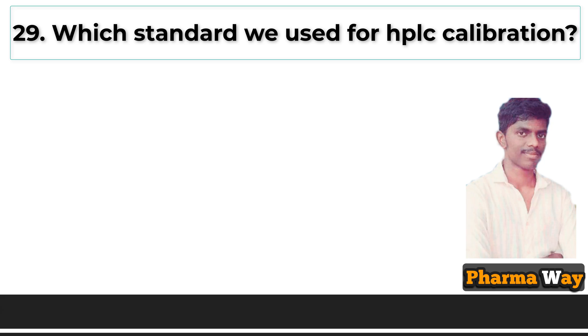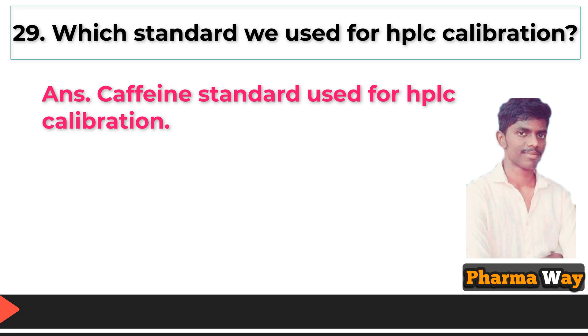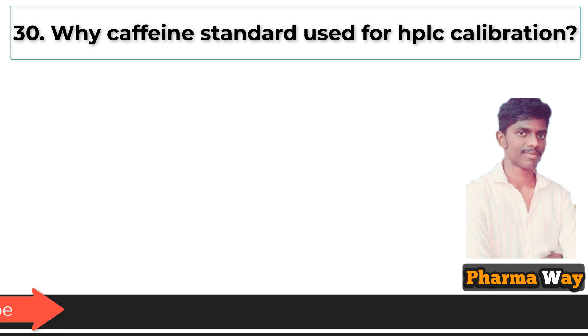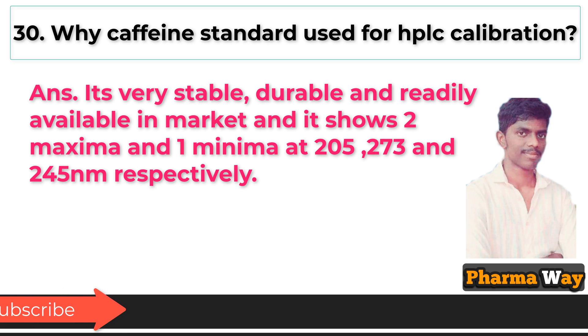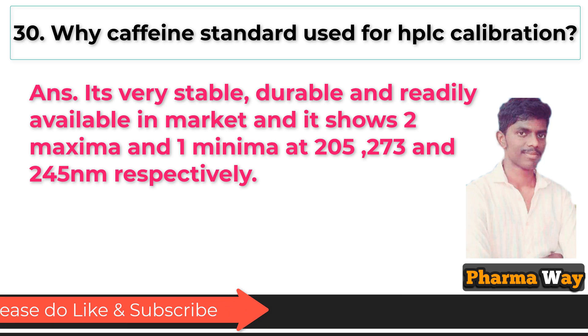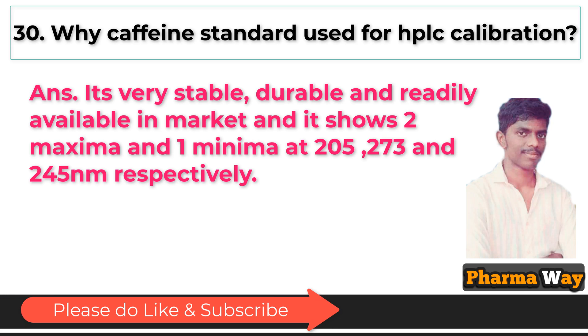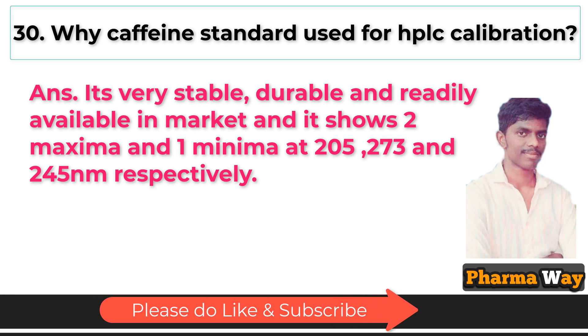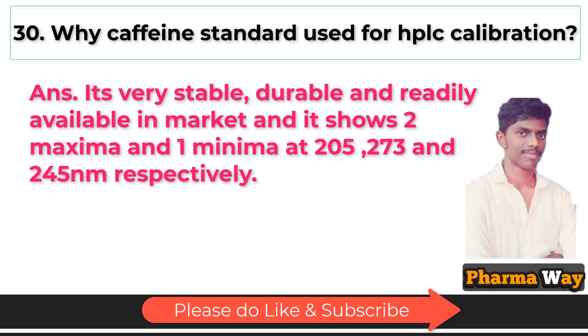Which standard is used for HPLC calibration? Answer: Caffeine standard is used for HPLC calibration. Why is caffeine standard used? It is very stable, durable, and readily available in the market, and it shows two maxima and one minima at 205, 273, and 245 nanometers respectively.